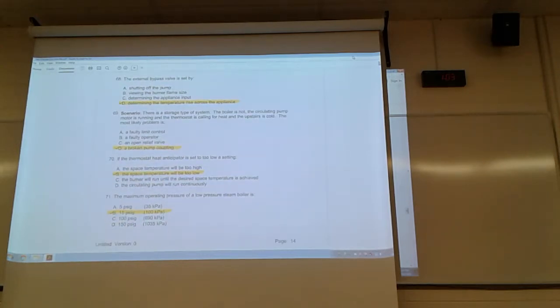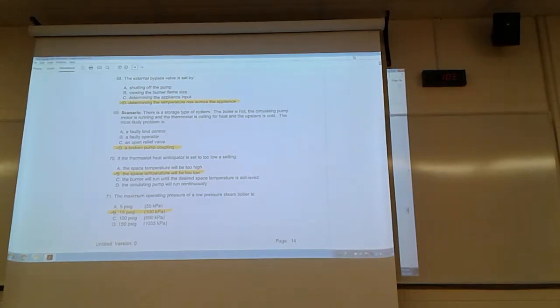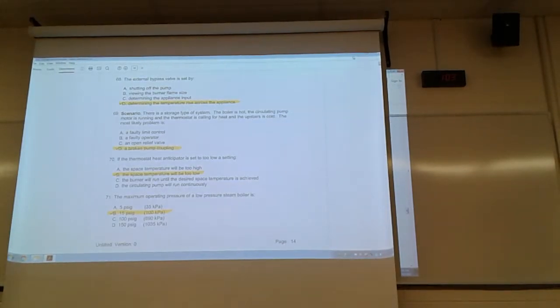69, there's a storage type of system. So you've got a hot water boiler. The boiler is hot, the circulating pump motor is running, and the thermostat is calling for heat, and the upstairs is cool. Okay, the problem is the pump is running, but the impeller is not, and it's not circulating water, so it's because of a broken pump coupler.